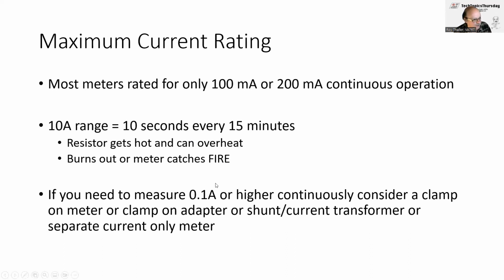And the recommendation is, if you really want to measure things more than 100 or 200 milliamps, get yourself a clamp meter, and I'll show you some examples of that. Or get yourself a shunt or current transformer and a separate meter that only measures AC current or DC current, and not a general purpose meter. Like if you want to measure 23 amps that your radio might want to use, then get yourself a meter that's designed just to measure 12 volts, 23 amps, and that's it, rather than a multimeter.